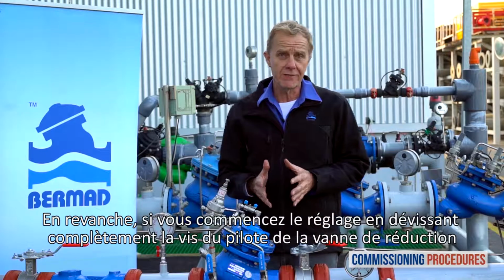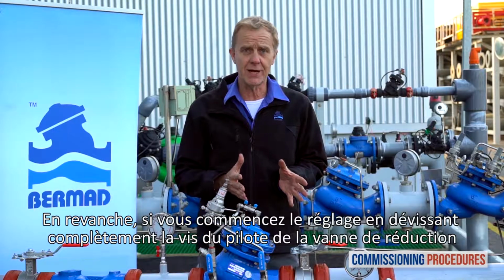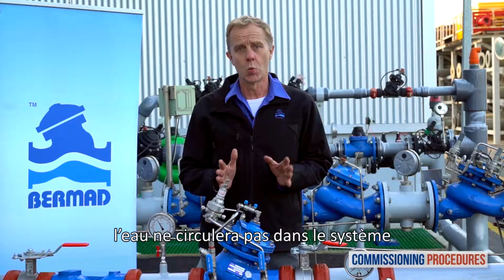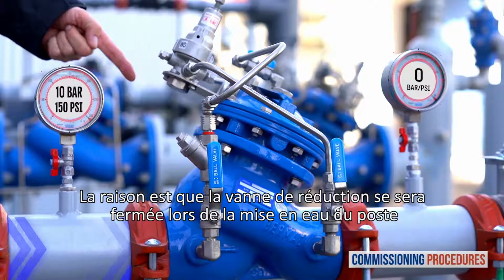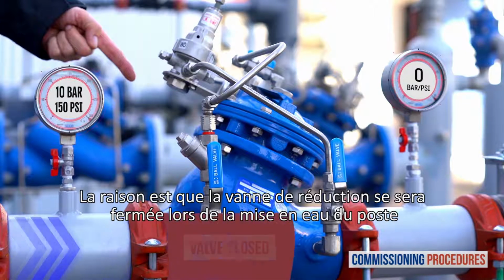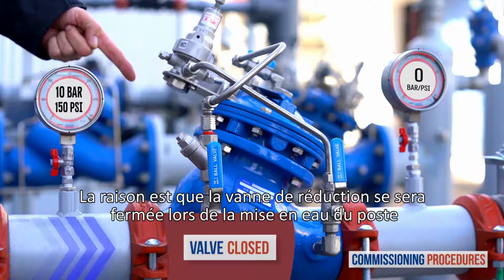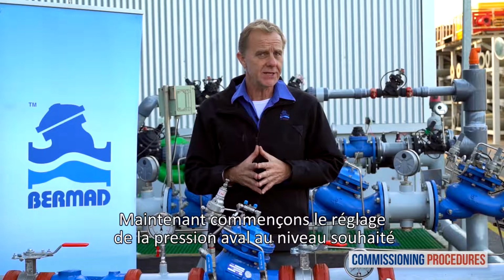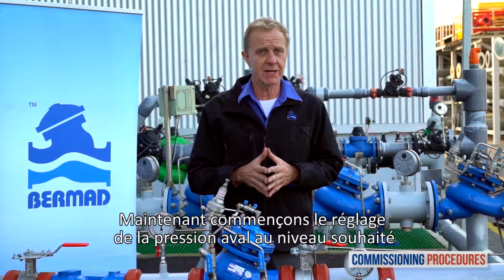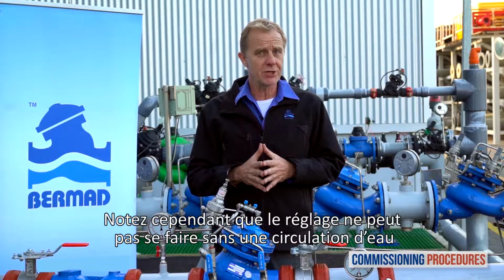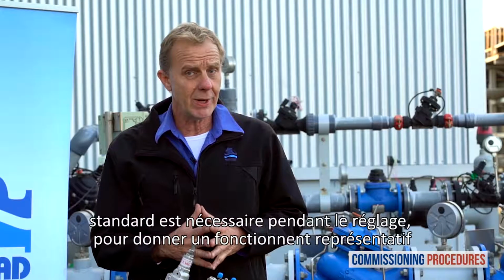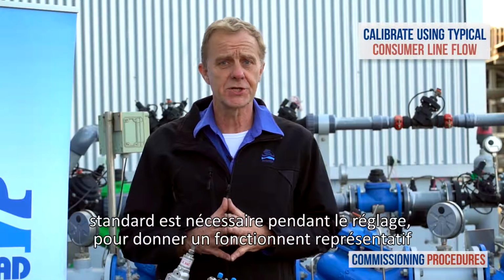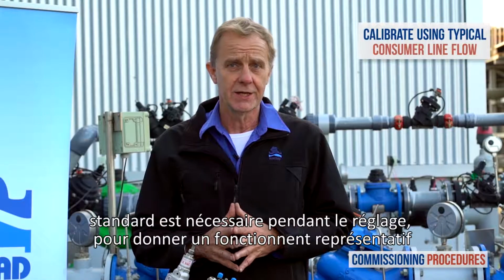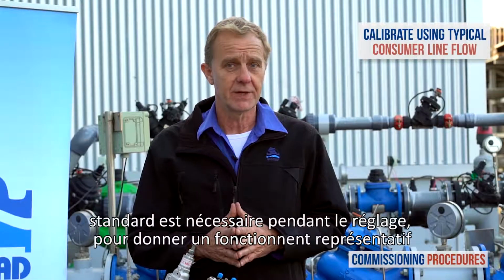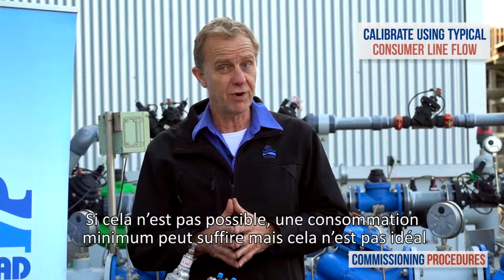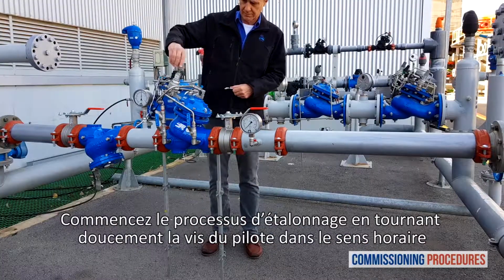On the other hand, if you prepared for pressure calibration by releasing the pilot adjustment screw of the reducing valve, water won't flow through the station. The reason is that in this case, the main pressure reducing valve will have closed shortly after introducing flow to the station. Now, let's calibrate the downstream pressure to the desired level. Note that the calibration cannot be done without flow. To simulate actual conditions, you should have a typical consumer line open while calibrating. This should get you an average system flow rate. If this is not achievable, a minimal flow rate will suffice, though not ideal.